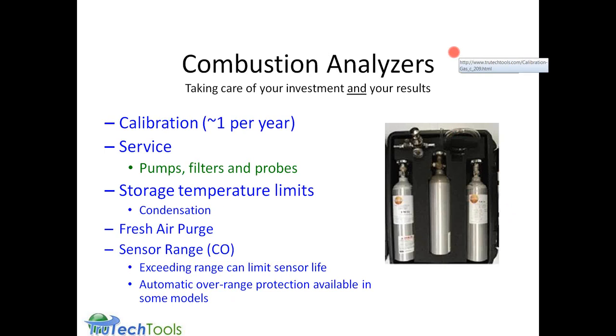So just a little bit on service and maintenance of the meter. You want to take care of the meter, because if you take care of the investment you made, it helps you perform and get the correct results. We recommend calibration about once a year. That would be calibration mainly for carbon monoxide. Most of the other parameters in it, temperature, pressure, and even oxygen are not calibratable. The oxygen is a reference that's always done when the meter starts up off of room air.